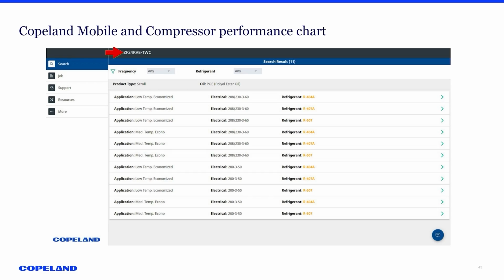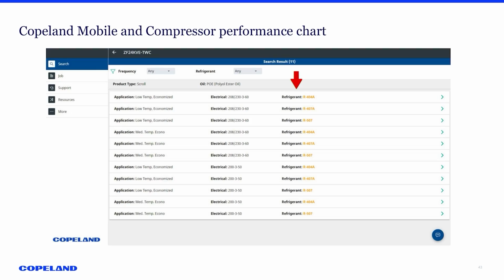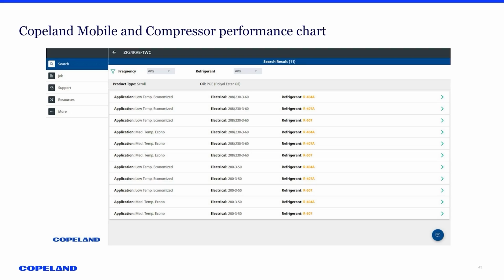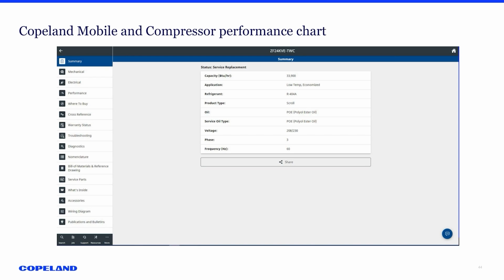So in my example, I picked a ZF24KVE compressor, okay? So we have to pick whatever application we're dealing with and what the refrigerant is. So we have 404A, 507. That's pretty much it with this one. Some compressors will have a lot of different refrigerants in there. And then the different voltages. When you're looking at the app, you can see on the left side here, I'm going to go to performance in a second. That's where you can actually see that performance chart that we were just looking at.